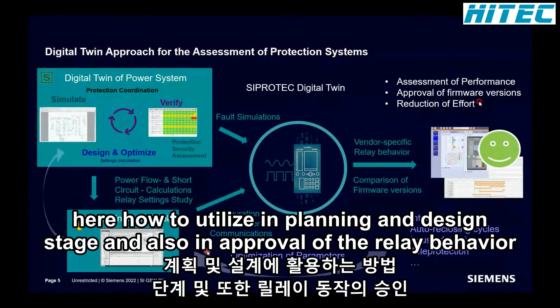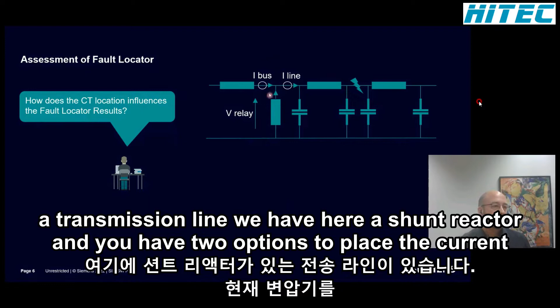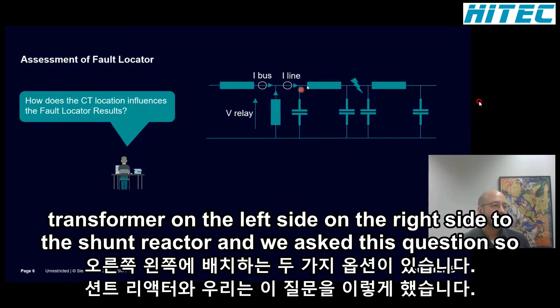So just to give a short example of how we utilize this: how does the CT location influence the fault locator results? We have a transmission line and a shunt reactor. You have two options to place the current transformer, on the left side or the right side of the shunt reactor, and we ask this question.